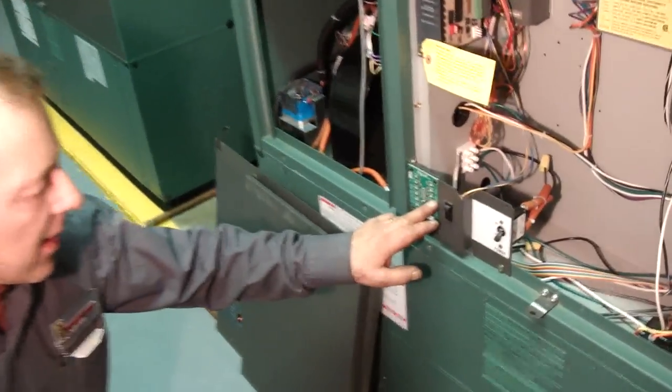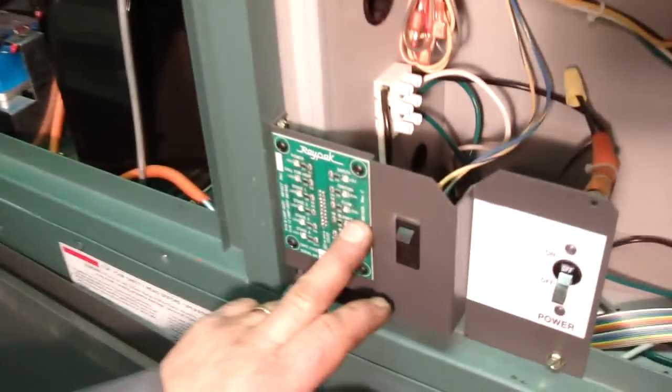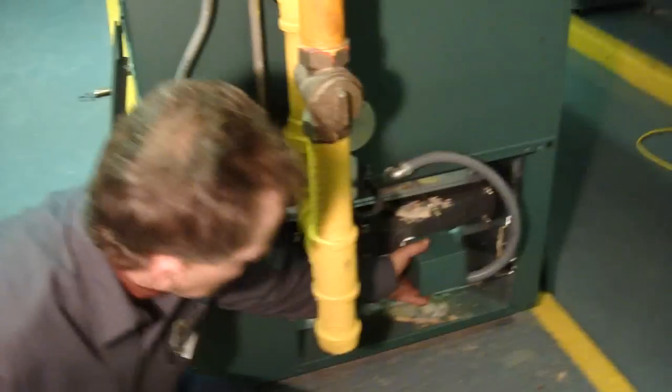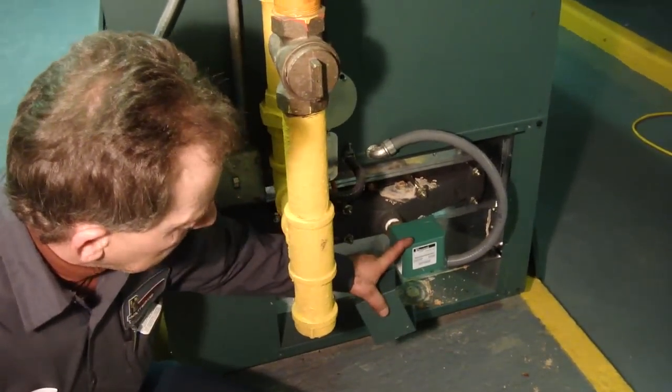In the event your flow status indicator is not lit, what you want to do is check the operation of your pump. From there you want to check your flow switch, which is located at the back of the boiler.